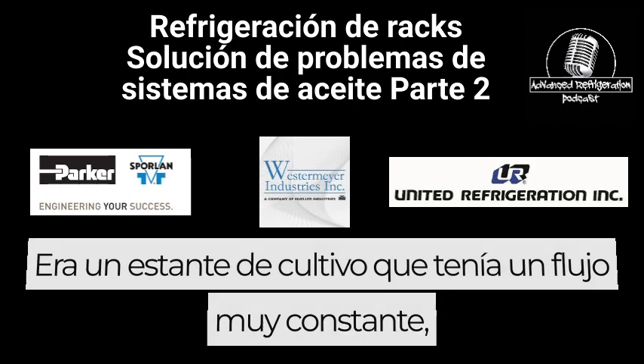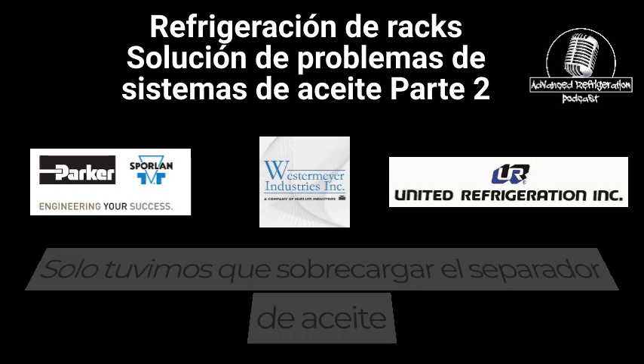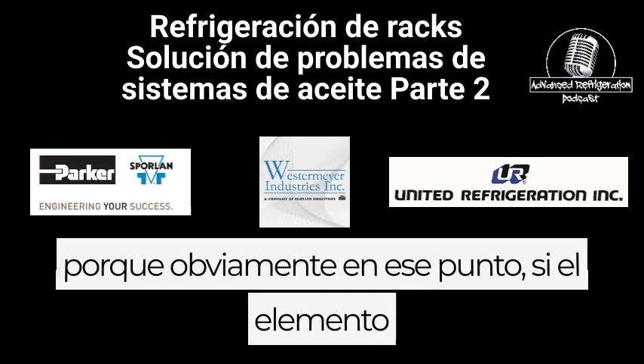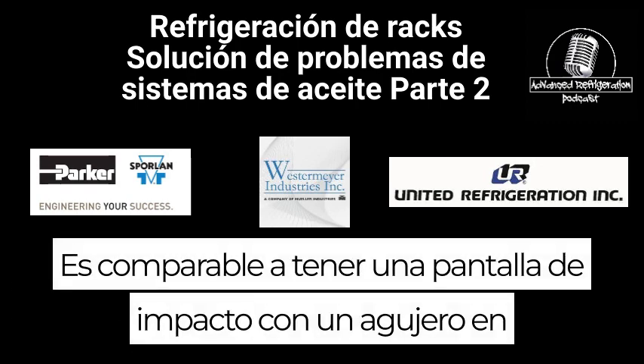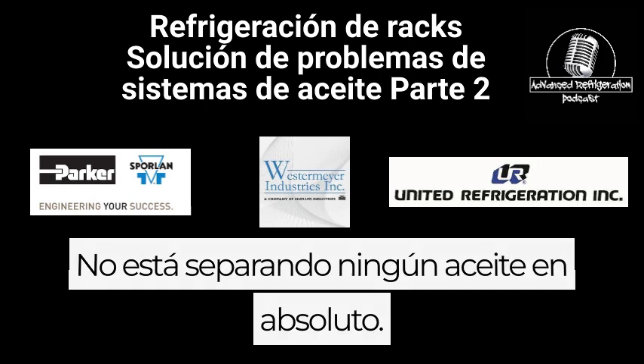Thank goodness it was a scroll rack that had very constant flow, so it wasn't really shooting a lot of oil through. We just had to overcharge the oil separator, because obviously at that point, if the element isn't in there, it's not separating any oil. It's comparable to having an impingement screen with a hole in it, or a regular coalescing element with a hole in it. It's not separating any oil at all.